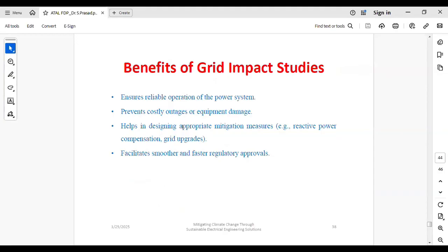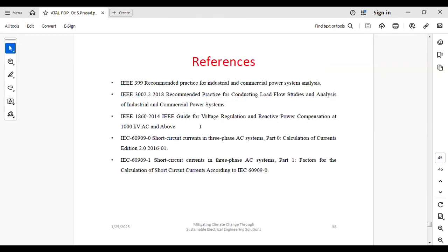So that's why, and it helps in designing appropriate mitigation measures. Example, reactive power compensation, grid upgrades. What should be the size of the reactive power needs to be installed at the PV end? That will be decided based upon the studies. That's why we are performing these studies. So the other references.